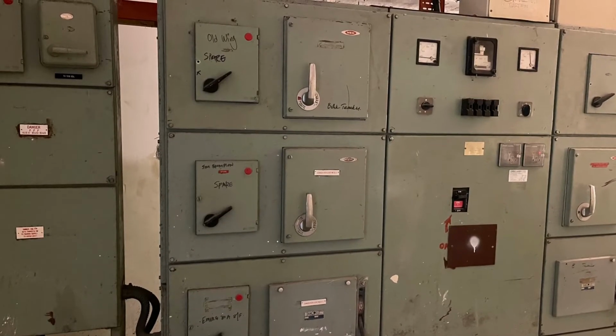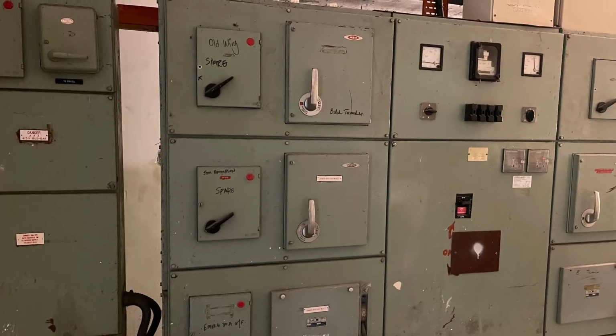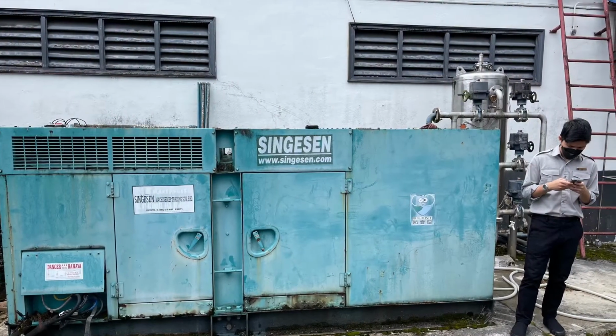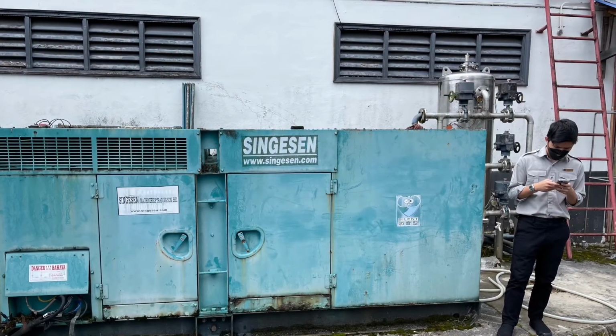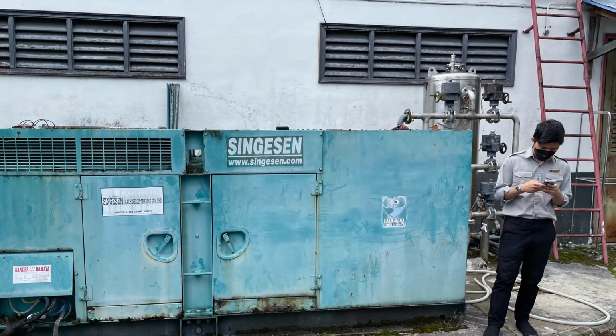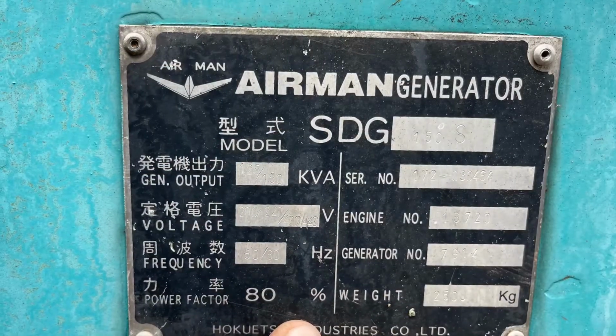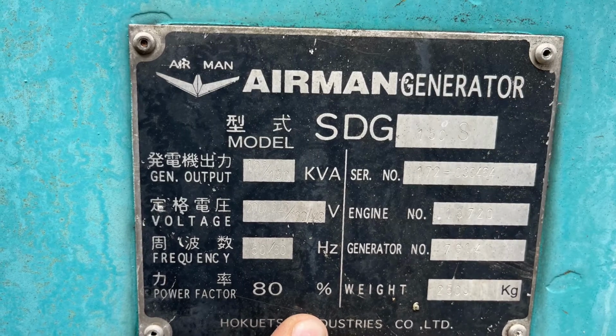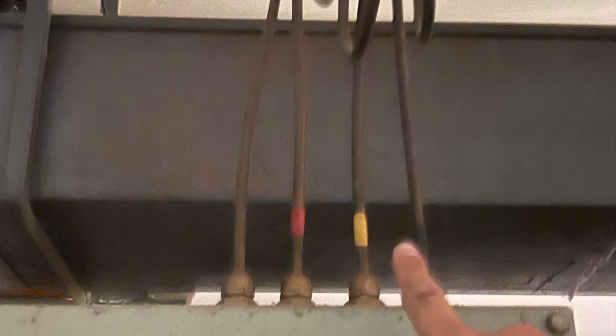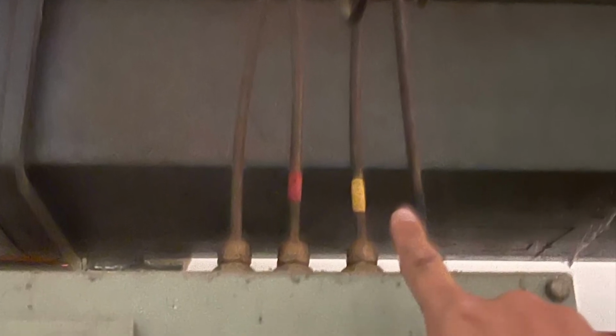Okay, after the genset is able to start automatically and stop automatically, therefore there was no problem with the genset. However, we don't know why the MCCB was off and set to off mode initially during the checking. Okay, never mind. So this concludes my inspection and genset test run.